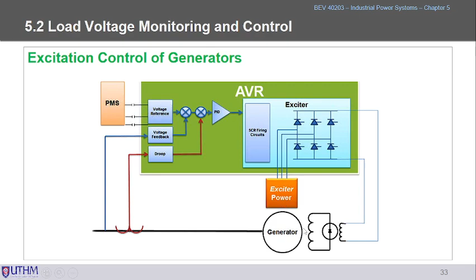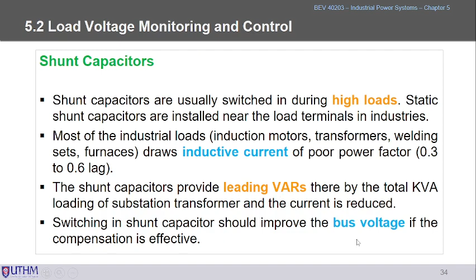The shunt capacitor is normally installed at the load level and the load bus. Normally, if we have a lot of motor loading, it draws inductive currents, which makes our power factor poorer. It's about 0.3 to 0.6 lagging, so that's why we need to compensate it back using the shunt capacitor. At the same time, we can also regulate back the voltage at the bus there.